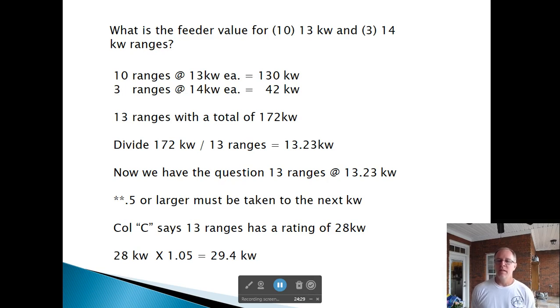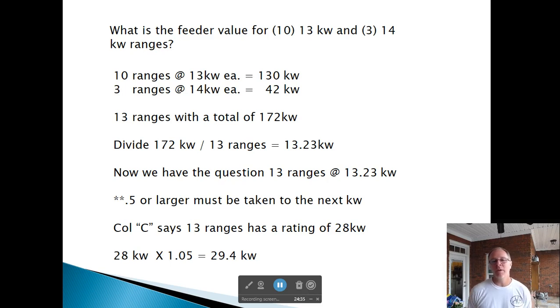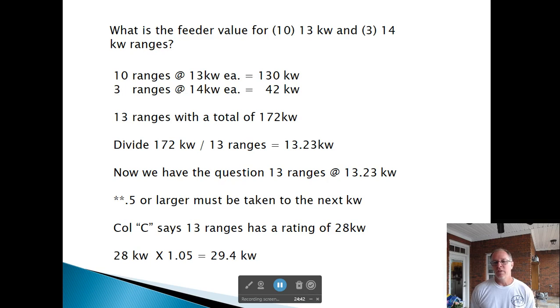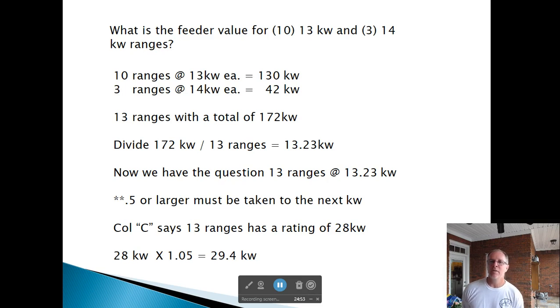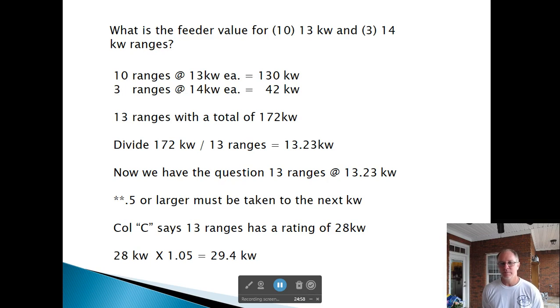Here's another example: 10 ranges at 13 kW equals 130 kW, plus three ranges at 14 kW equals 42 kW — total 13 ranges and 172 kW. Average is 13.23 kW, so we use 13 kW. Column C for 13 appliances gives 28 kW, and we add 5% for being 1 kW over 12.